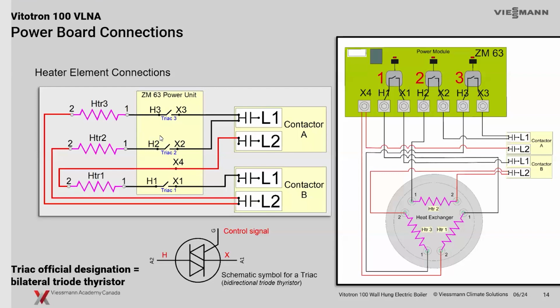So just a little bit more detail. There are our contactors A and B that we just saw on the previous slide, and they're going to go through our fixed high limit. So the power to that contactor goes through the fixed high limit. As long as that fixed high limit's closed, those contactors are engaged, and they're powering up our main board here. And of course, through the triacs, we can stage these different elements 1, 2, and 3 to turn on and stage that should we need, a low load day. We don't need all 3 contactors. It's going to stage those contactors to save you a little bit of energy and power.